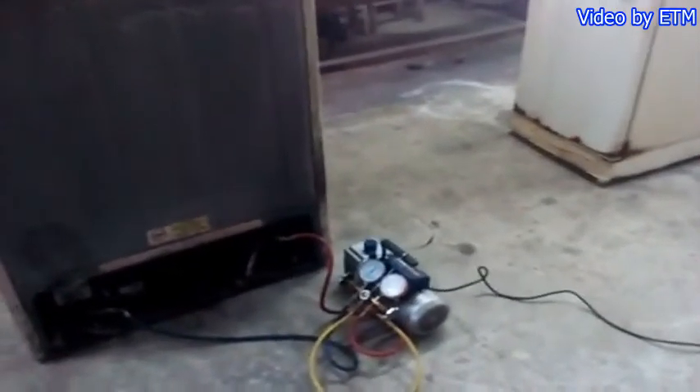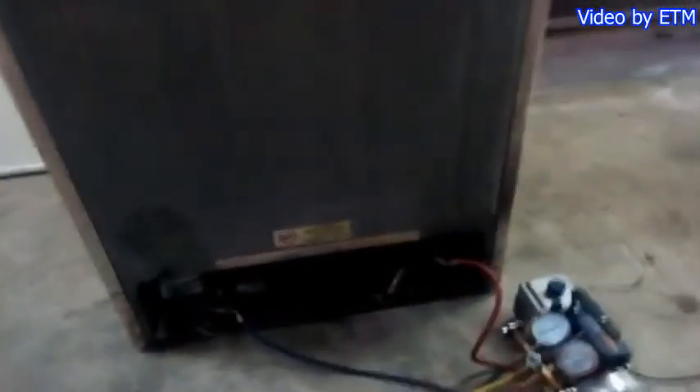This is the refrigerator being finished. Two refrigerators being repaired. I'm currently working on one R12 converted to 134A. The other one had a problem with the thermostat and filter dryer — the thermostat was stuck on and the filter dryer was clogged. Both have been replaced now.